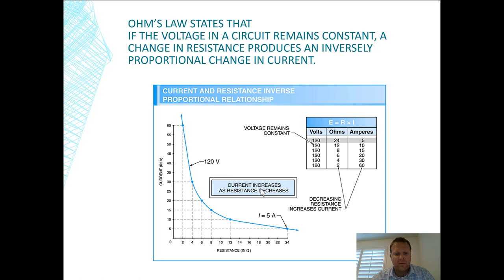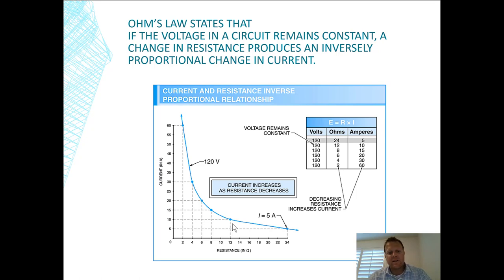This concept is important because you'll hear about something called a voltage drop. You have an electrical conductor — usually a wire, copper or aluminum — that allows electricity to travel but has resistance to it. The longer the conductor or the smaller its size, the more resistance at certain voltages. That's the main context where I've heard about volts, resistance, and amps — dealing with voltage drop over distances.